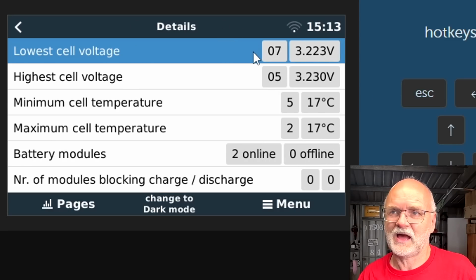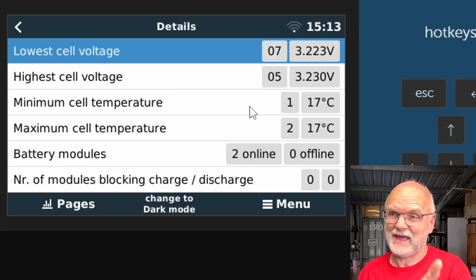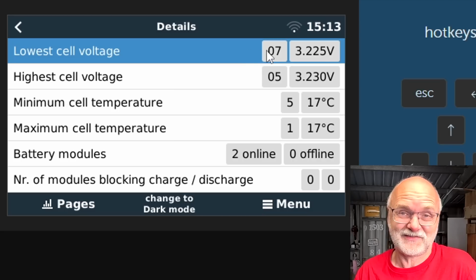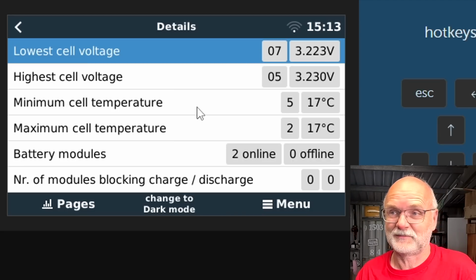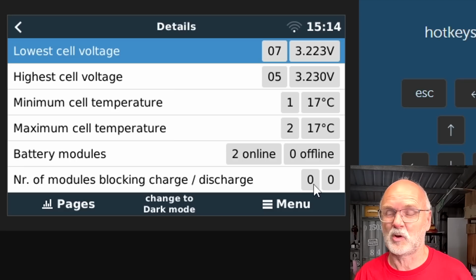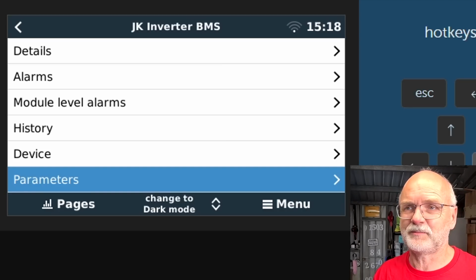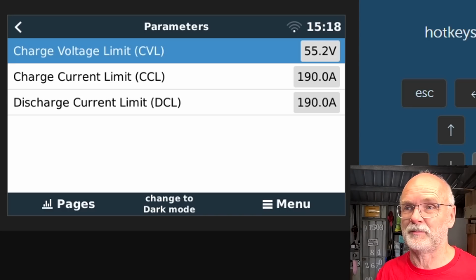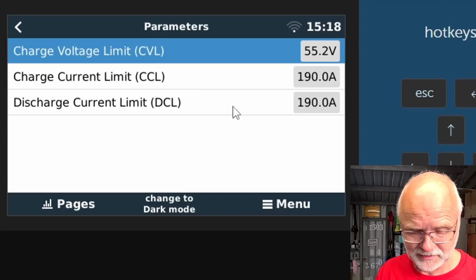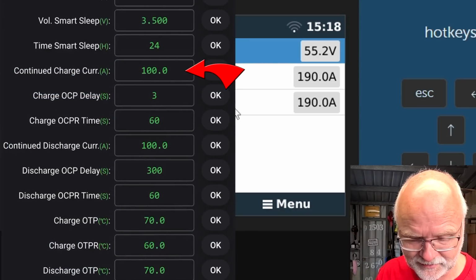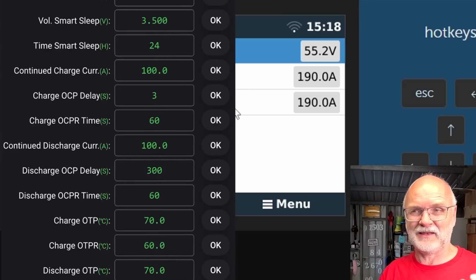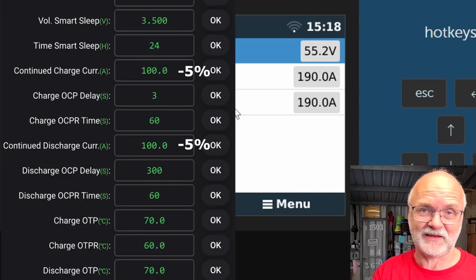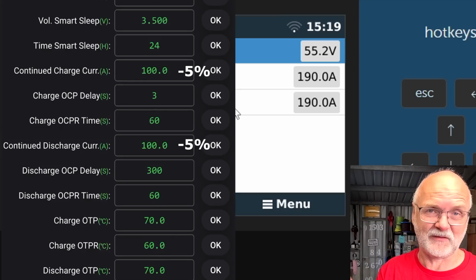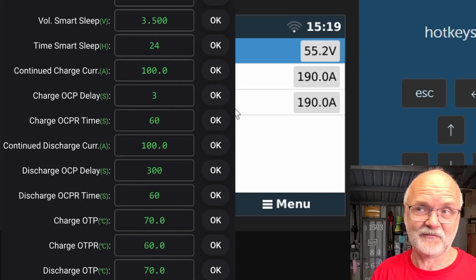So here in the Victron VRM the JK inverter BMS shows up, and if we go into the details we can see the highest and lowest cell voltage, but we still don't know which battery that actually is in. We only know there's a cell number 7 somewhere in one of these batteries, and it's the lowest cell, but we don't know which battery it's in. It also correctly shows we have two batteries online, a master and a slave, and neither is currently blocking charging or discharging, so everything is fine at the moment. If we look at the parameters of these two BMSs combined, we can see we've got a charge current limit of 190 amps and a discharge current limit of 190 amps as well. This is because in the settings we've set a continued charge current of 100 amps and a continued discharge current of 100 amps. The software takes away 5% of the amount you've set in the app, so from 100 amps, 5% is 5 amps, and this reduced amount of current is reported to your inverter or the Victron system.